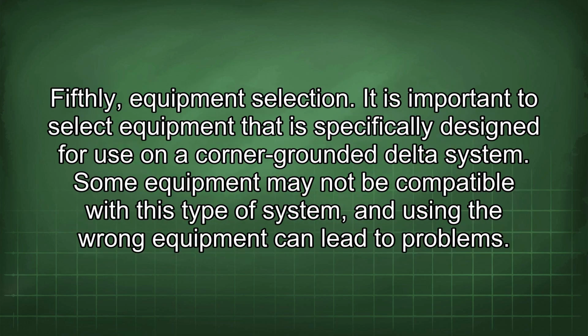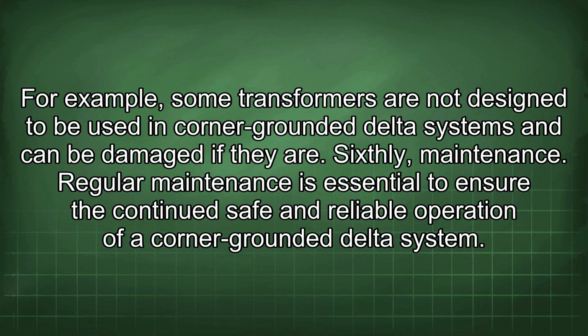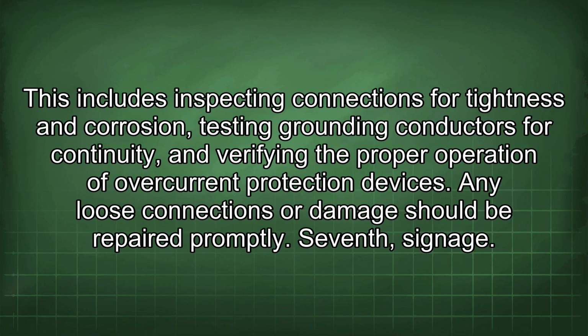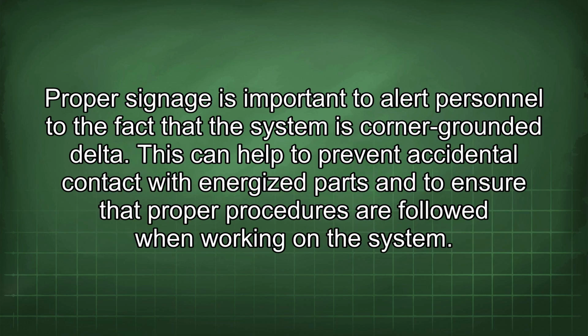Fifthly, equipment selection. It is important to select equipment that is specifically designed for use on a corner-grounded delta system. Some equipment may not be compatible with this type of system, and using the wrong equipment can lead to problems. For example, some transformers are not designed to be used in corner-grounded delta systems and can be damaged if they are. Sixthly, maintenance. Regular maintenance is essential to ensure the continued safe and reliable operation of a corner-grounded delta system. This includes inspecting connections for tightness and corrosion, testing grounding conductors for continuity, and verifying the proper operation of overcurrent protection devices. Any loose connections or damage should be repaired promptly. Seventh, signage. Proper signage is important to alert personnel to the fact that the system is corner-grounded delta.